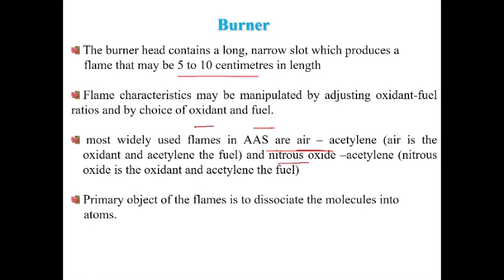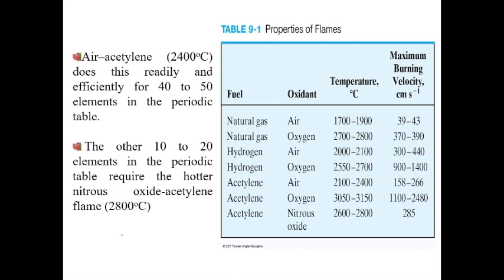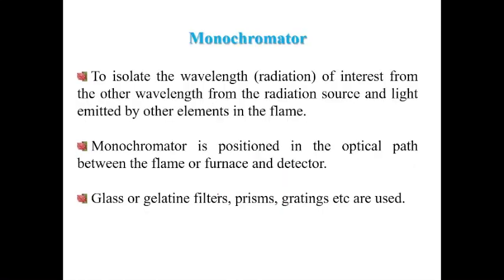Flame characteristics can be manipulated by adjusting the oxidant-to-fuel ratio and choice of oxidant. Most commonly, flames in AAS use air-acetylene (air as oxidant, acetylene as fuel); alternatively nitrous oxide-acetylene can be used. Air-acetylene can determine 40–50 elements; for elements requiring higher temperatures (~2800°C), nitrous oxide-acetylene is used. The primary objective of the flame is to dissociate molecules into atoms.